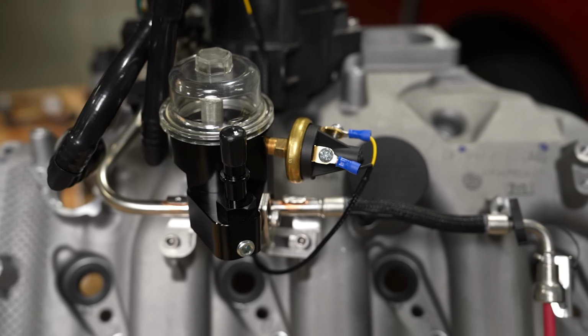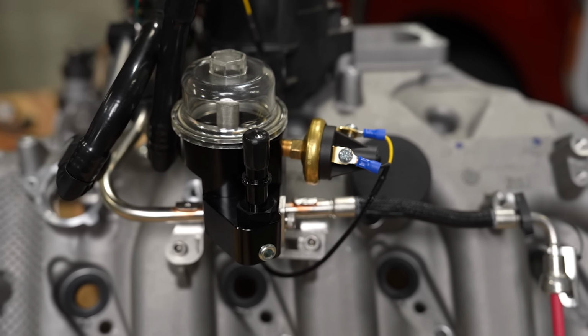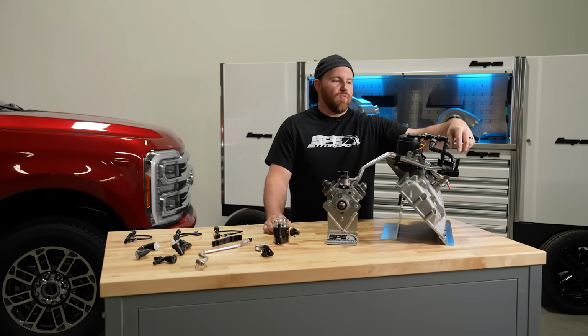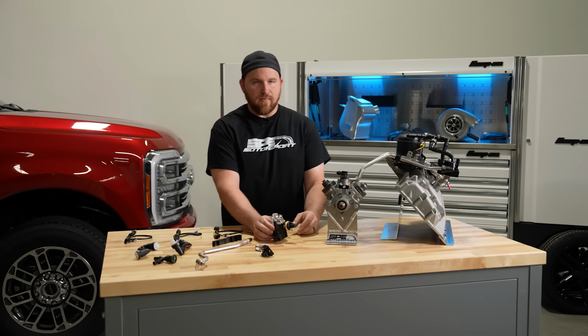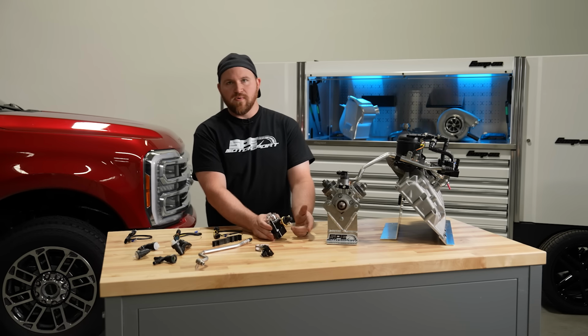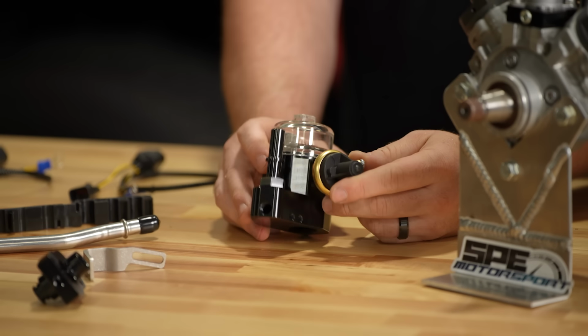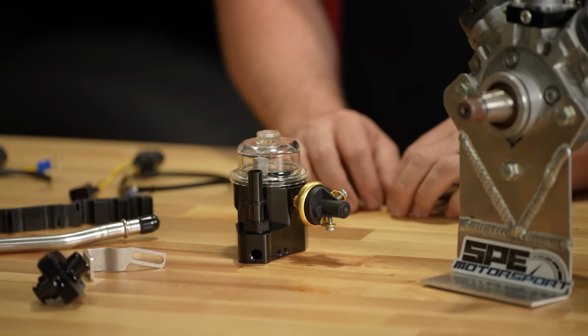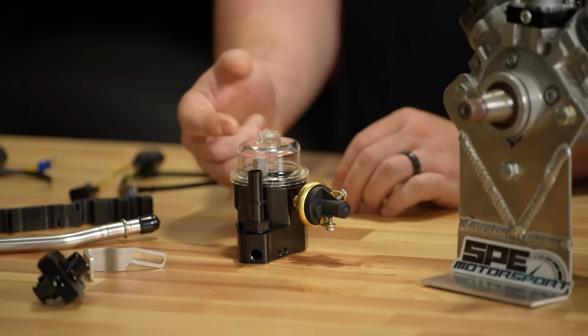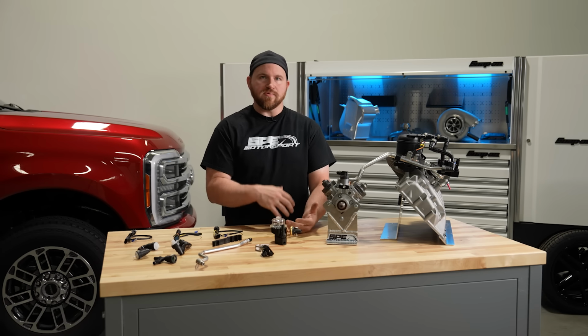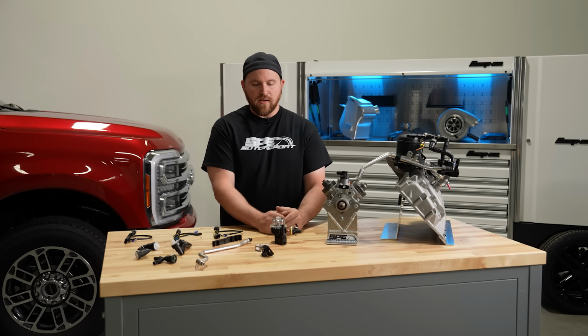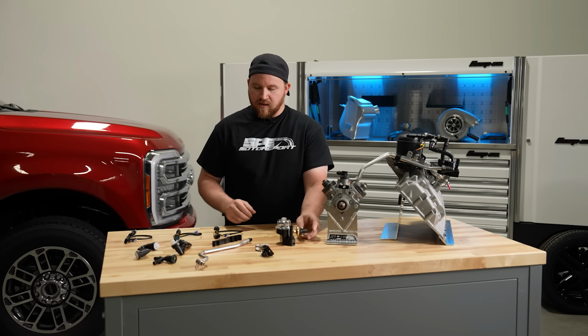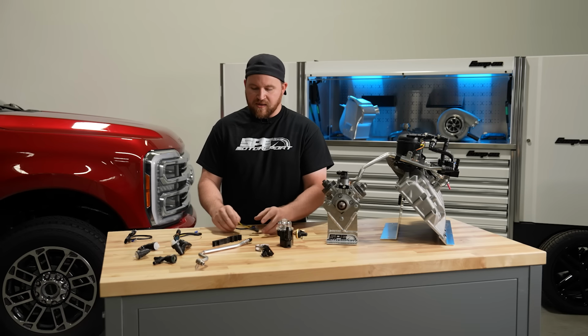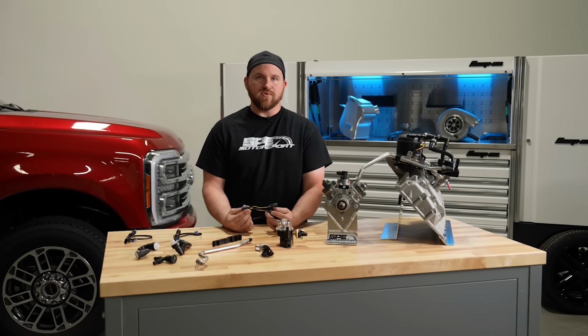As the return fuel comes out of this pump and goes back to our filter assembly, we have what we call a contamination sensor, which is very simple. It's a pressure style sensor that monitors pressure drop. So if our filter or screen becomes clogged, we created a setup connecting a wiring harness to the pressure sensor that then taps into the factory fuel pressure switch on the truck.